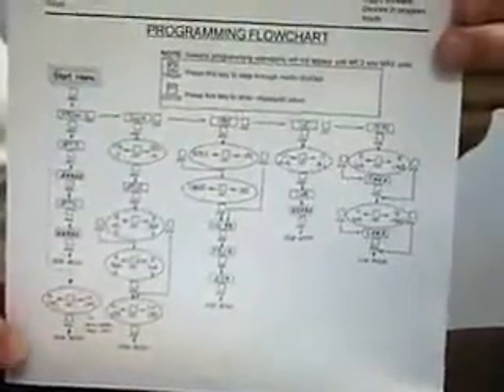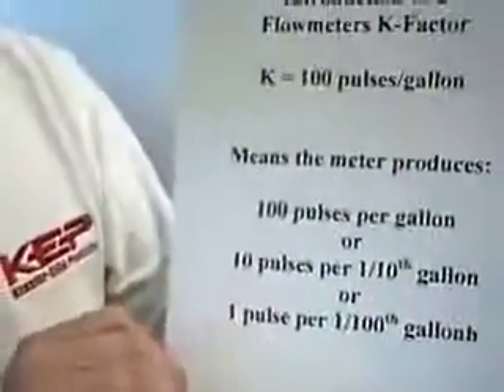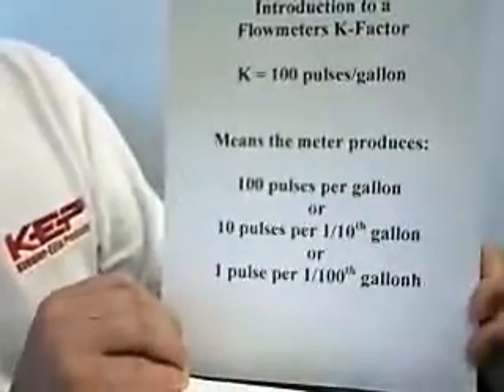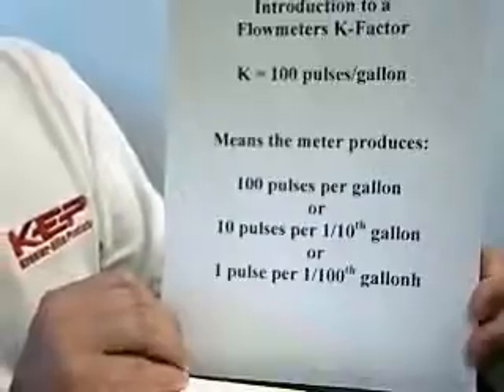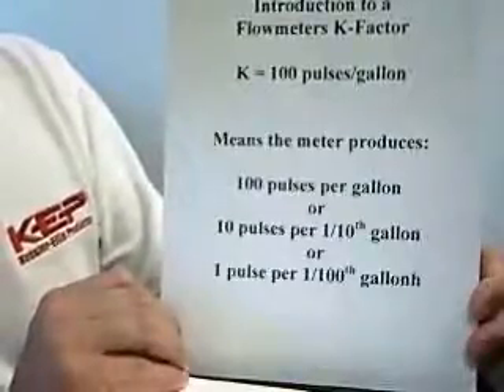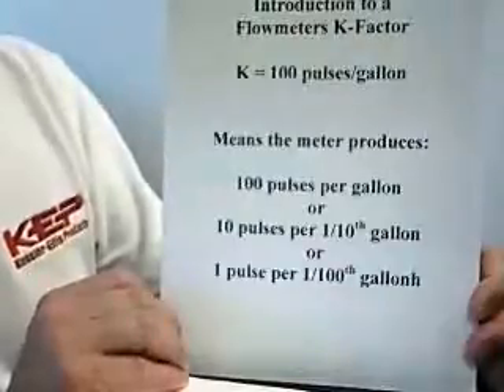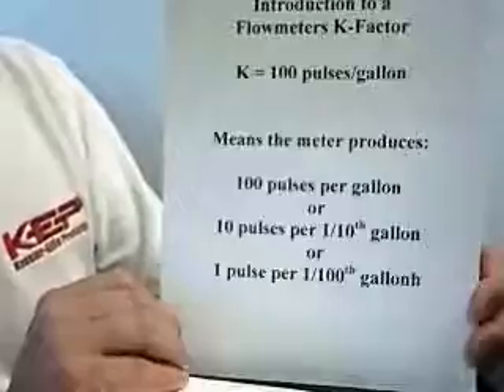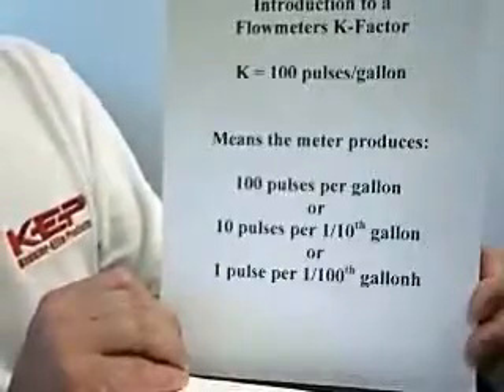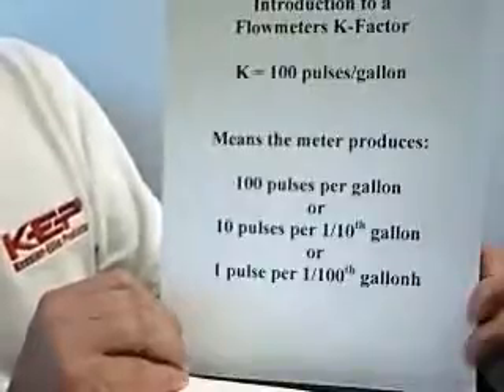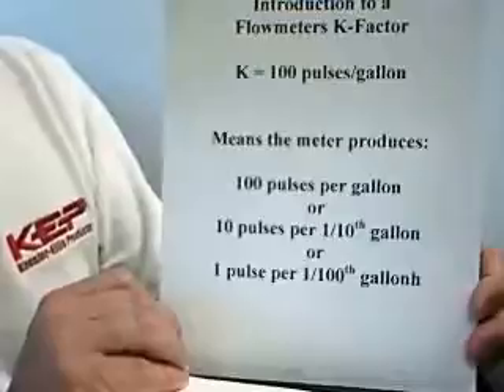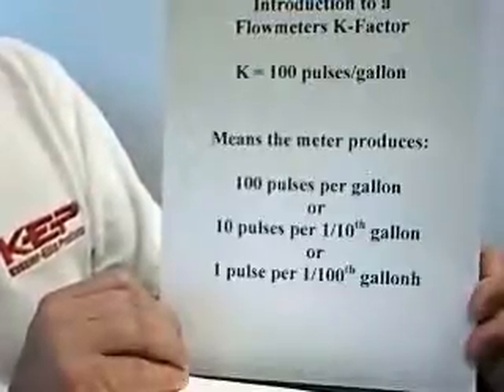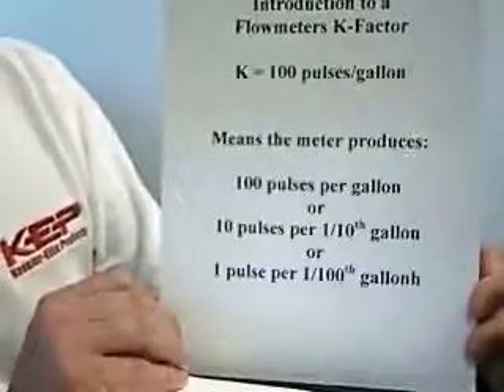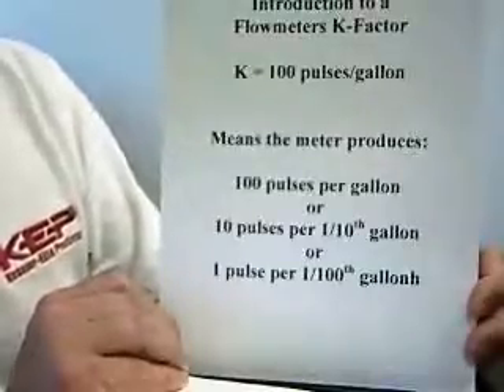Now, before we begin, I want to introduce to you the concept of flow meter KFactor. The flow meter KFactor is basically the calibration constant for pulse-producing flow meters. This value is often provided on a measurement certificate that accompanies each sensor, but it may also be actually stamped on the body of the flow meter or on a metal tag affixed to it. And it's normally expressed as a number, in this case 100 pulses per gallon. Now what that means is that that flow sensor produces 100 pulses for every gallon passing through it.